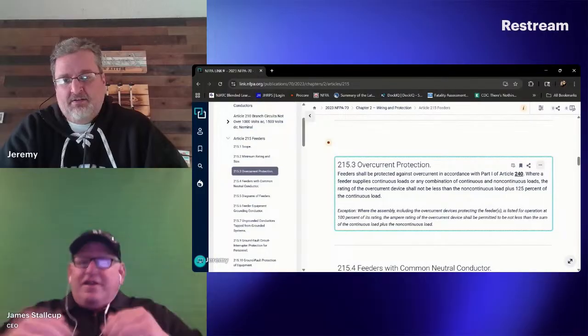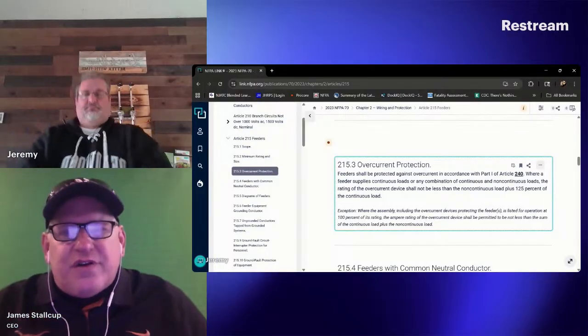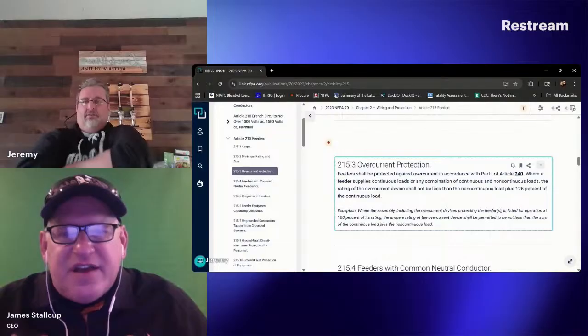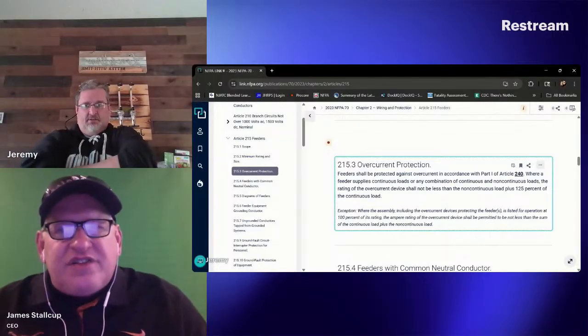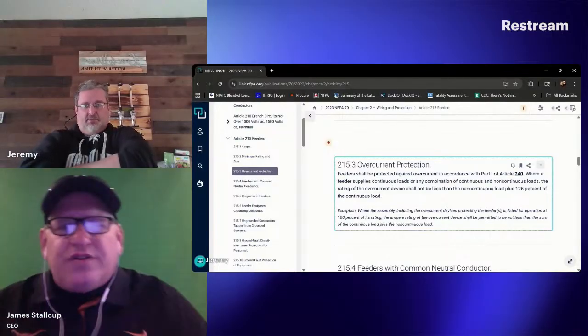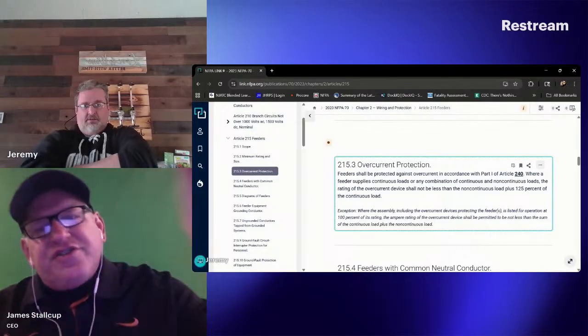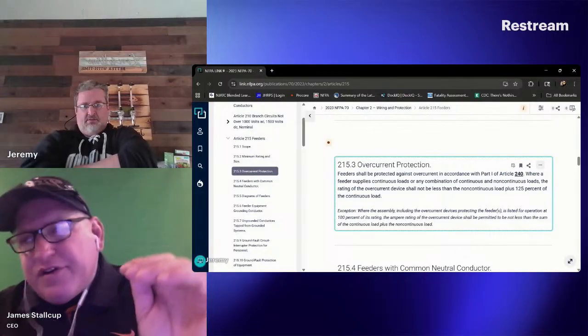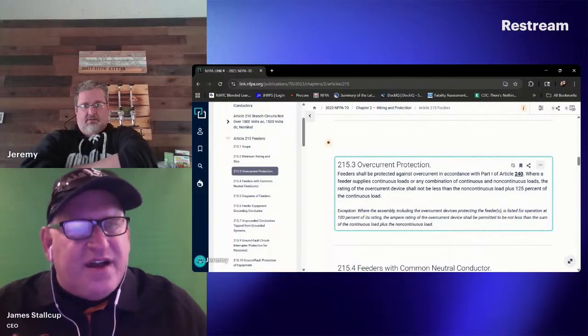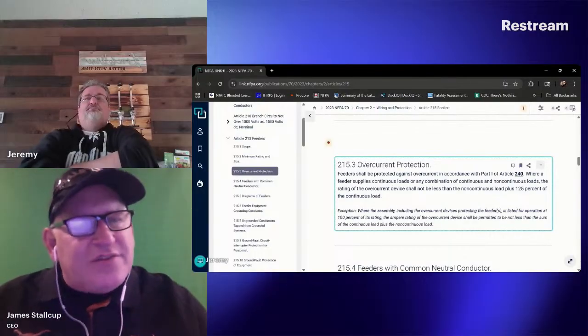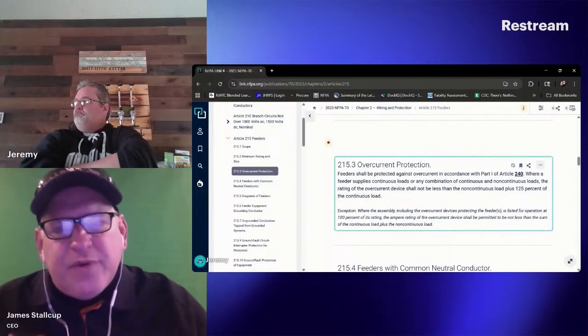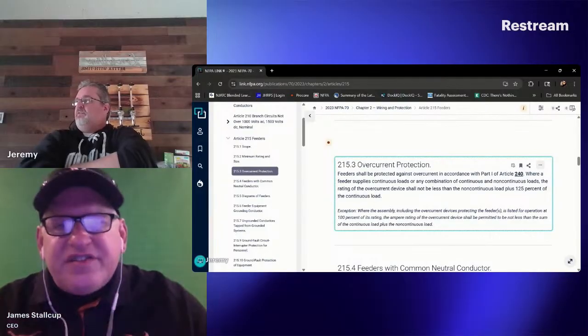Oh my God. You size the conductors and overcurrent device exactly the same. Once you've got the conductor size already done, then it tells you what to do for the protection of conductors in Article 240 that literally deals with overcurrent protection device. And it says, unless otherwise permitted or required in 240.4A through H. It literally says it. Yes.